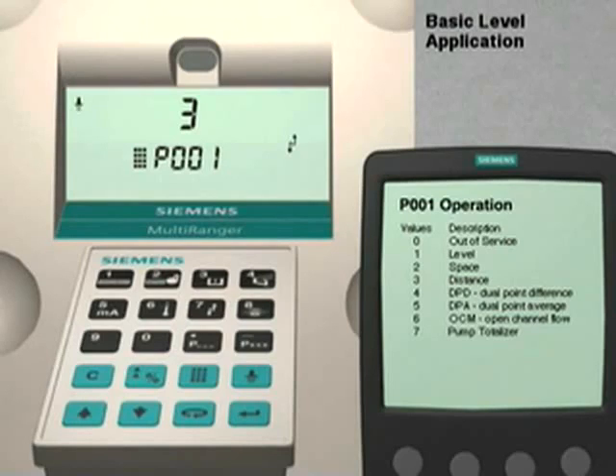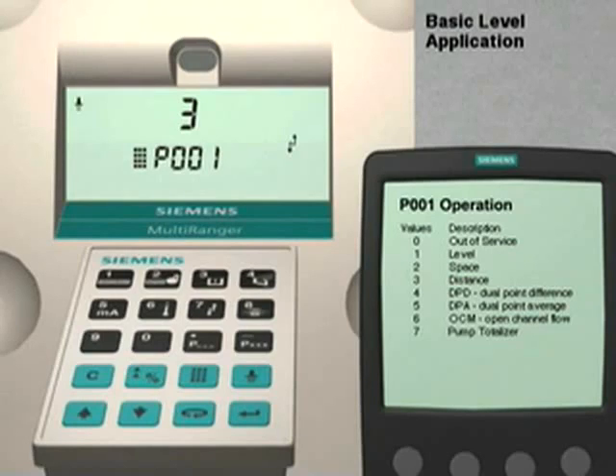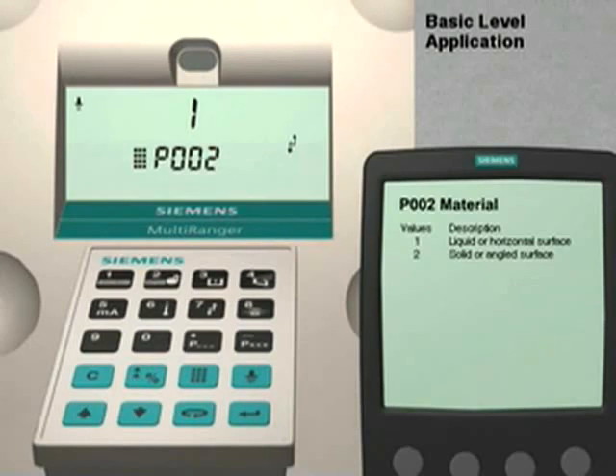For our application, we want to measure the level, or in other words, the height of the liquid in the vessel. According to the manual, parameter 1 for a level measurement should be set to a value of 1. To do this, simply push the number 1 key followed by the Enter key. To go to the next parameter, press the up arrow key.